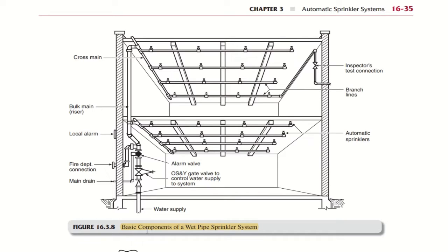So here they have shown the figure. You can see chapter 3, automatic sprinkler system. You need to remember that it definitely covers the types of sprinkler systems like wet, dry, pre-action and deluge. This figure shows the basic components of a wet pipe sprinkler system. Here you have the branch piping with the sprinklers, this is the cross main, and this is the riser. You can call this the bulk main or riser. Here you have the alarm check valve assembly and the water supply from the underground network or from the pump.